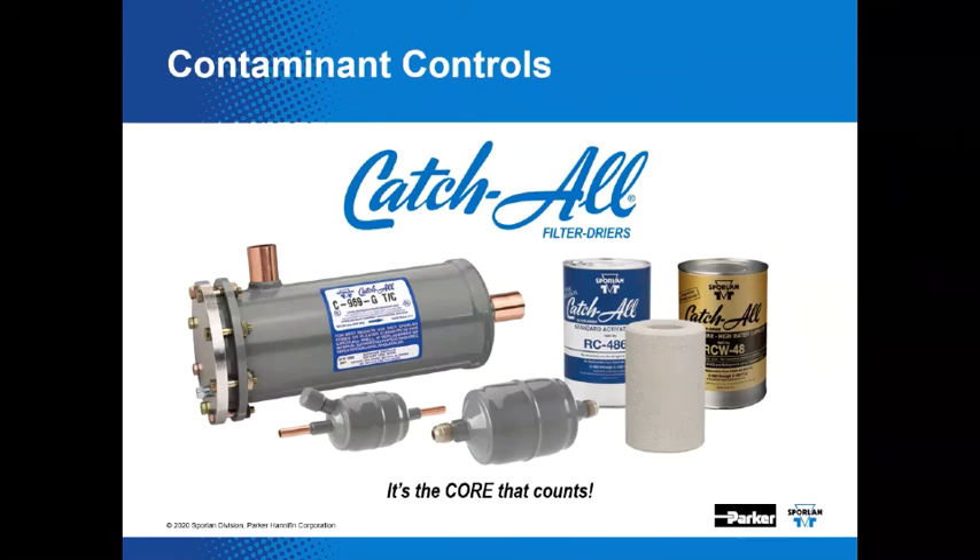A question came in noting that if you use an oversized liquid line dryer on close-coupled package systems, the technician will need to compensate for the extra liquid holding capacity of the dryer. That is exactly correct — once you put more volume into the liquid line, you have to add refrigerant charge to fill it. Go back, set up your system, look at your See-All to make sure you don't have any flash gas, and double-check to make sure you have proper subcooling and superheat to the manufacturer's recommendations.